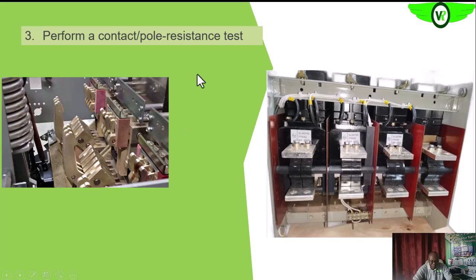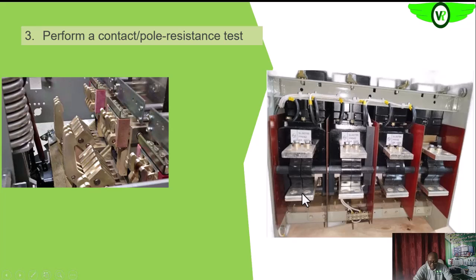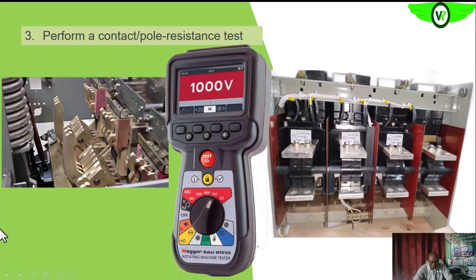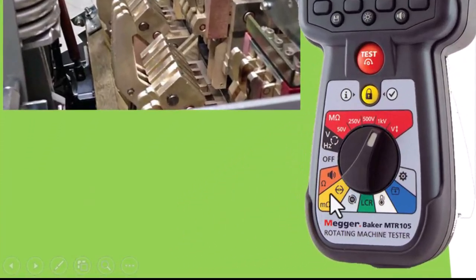Then we also want to perform the contact pole resistance. With the circuit breaker closed, we test between the two contacts, these two bars, the input and the output bars. That will help us verify the contact resistance. This is an air circuit breaker, so we have to close it first and test at the input and the output. The stationary contact is connected to this particular bar, and the movable contact is connected to this bar. So when it is closed, what we are actually testing is the contact resistance on the pole. We can use the milliohm section, or the low resistance section, of this meter.